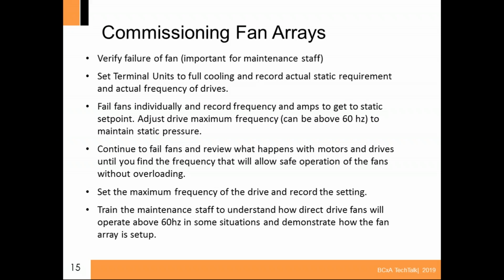And then I'll look at what the amperage is being drawn on the load side. I'm just saying the load side of the drive. And I'll look at that and I'll make a determination if I can go ahead and creep that frequency up. And sometimes I'll take the max frequency and change it from 62 maybe to 70 hertz. When I get to 70 hertz, I'll look at that amperage and see how close I'm getting to overloading the 3 motors. And then I'll trip off the second motor so that this 4-fan wall is running on 2 fans. And I'll look at that real close and make sure that the fans are not in an overloading condition at that maximum frequency that I set it at. So that if they have 2 fan fails, they're getting the maximum air out of that air handler that they can get.